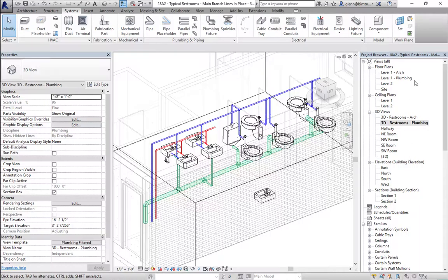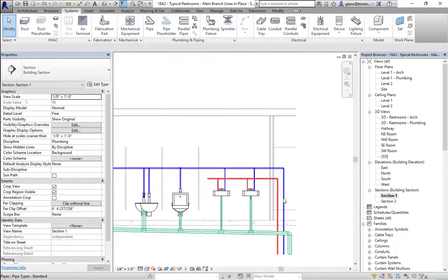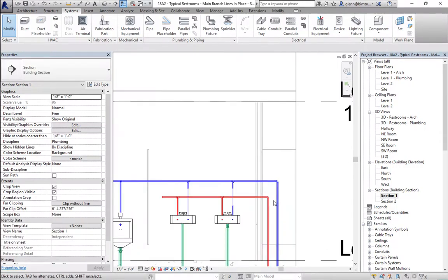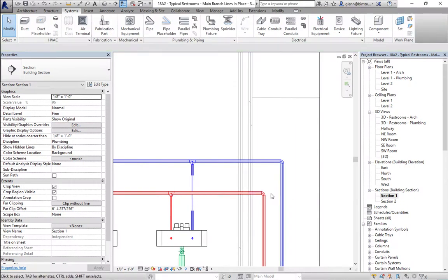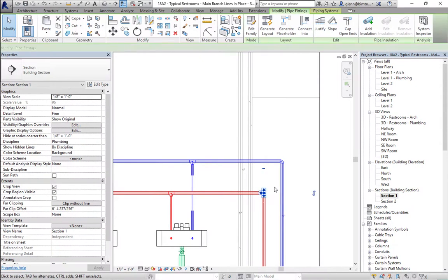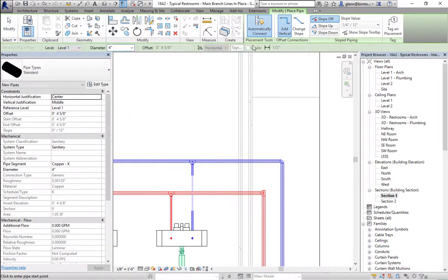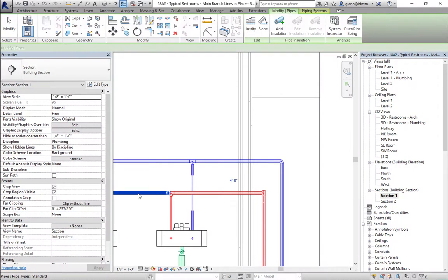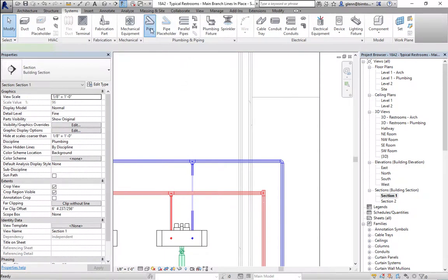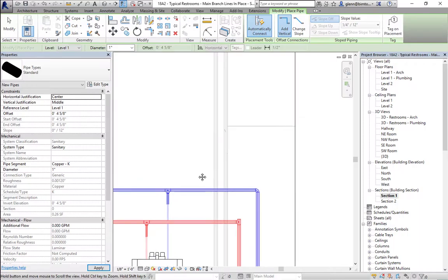Looking at it in section, my hot water is currently stopping here. I'll use Jordan's trick — place the open connector and run a pipe from there. I'll automatically connect it and run as a one-inch hot water pipe going up to the ceiling level. The same thing happens with piping as with ductwork: it tallies up all the flows, and if the flow actually needs a two-inch or two-and-a-half-inch pipe, it'll resize it automatically.